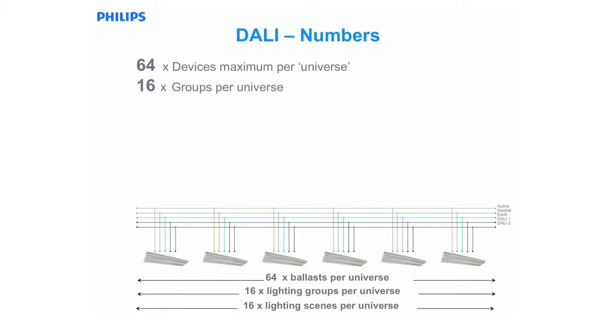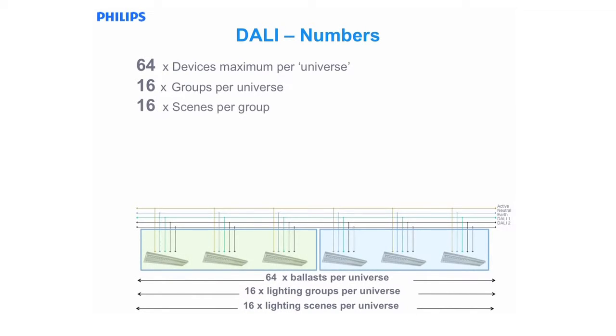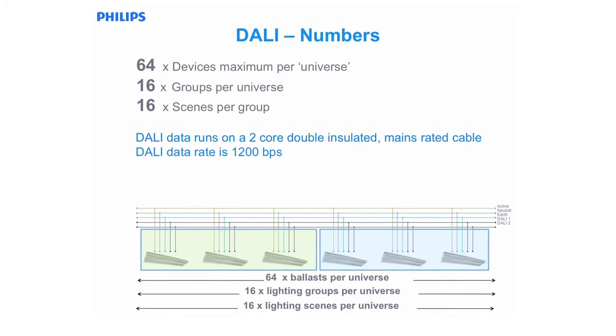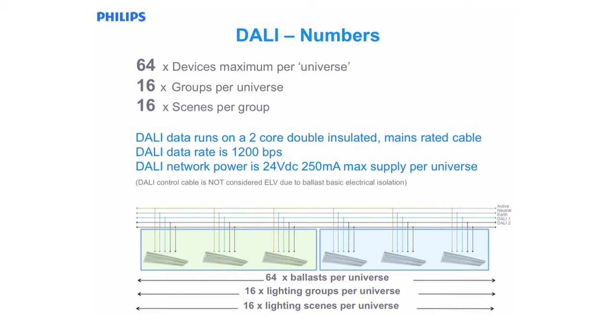The physical DALI network requires a 2-core cable. It must always be remembered that the DALI network only has functional isolation between the active power and the DALI network. It is essential to remember that the DALI network should always be considered as live for safety. This is quite a slow protocol in comparison to others used by computer networks. But as it is an event-based protocol dedicated for lighting control, that is not required to transmit large amounts of data, it is more than sufficient. The DALI network has a maximum supply of 250 milliamps.